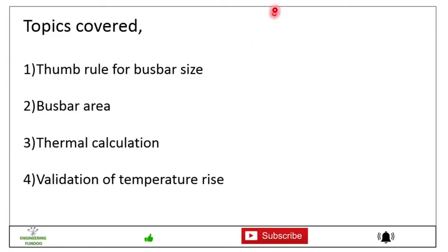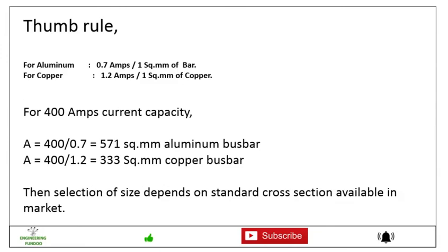And the last one will be the validation of the temperature rise, that is for the thermal validation. Friends, if we talk about the thumb rule, normally there is a general thumb rule that for aluminum busbar it will carry 0.7 ampere per square mm of the bar, that is one square mm cross section area, and for copper 1.2 amperes per one square mm of the copper bar it will carry the current.